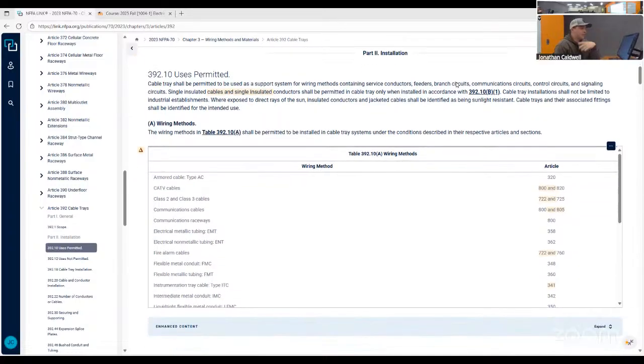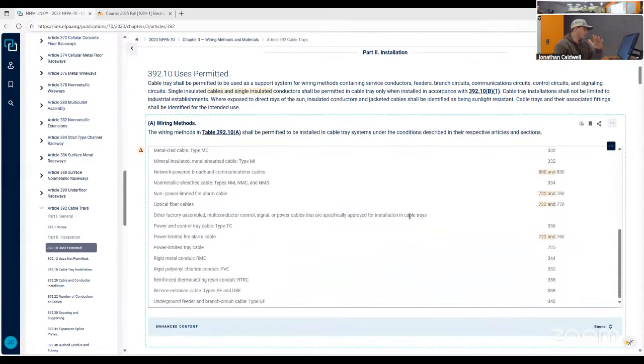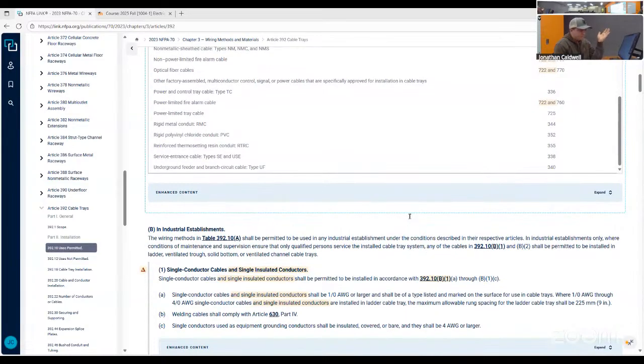So as you can see, cable tray ties into a bunch of stuff. It really does. It's probably one of the best ways to do it, instead of doing a conduit rack like you'd see in a commercial building. And then industrial, that is your conduit rack essentially. The only time you'll really see cable tray get used as a conduit rack is typically in an industrial setting. Trying to think of any other place where we've done it.